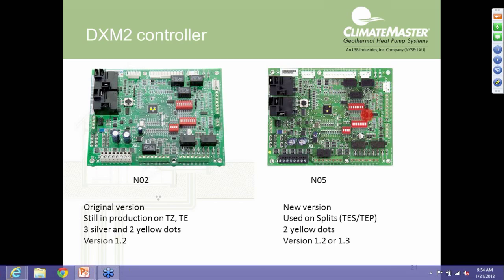Currently we're not using the AO1 jumper, but in some future applications we're probably going to be using it. Along with that, there are two additional terminal points here for the AO1 jumper. So if you get one of these boards for a replacement and you look at the N02, it does not have that jumper. Don't be alarmed. If you don't need it, it's just on there, it's not a problem. And the current version for both boards will be 1.2. In the case of the N05, there's also a version 1.3.